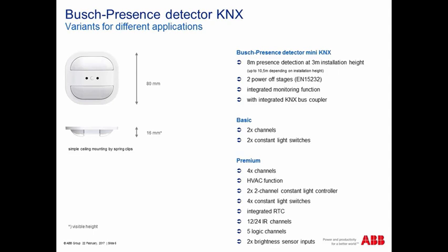And the premium one has also, of course, HVAC functionalities, but the most important benefit here is an integrated room temperature controller. That means if you think about an office application, you only need one device. Here is a fully integrated room temperature controller, so you don't need a further one inside the room. And the room temperature controller follows our so-called unified RTC standard. That means you have the same functionality as in our standard sensors and in our other products.